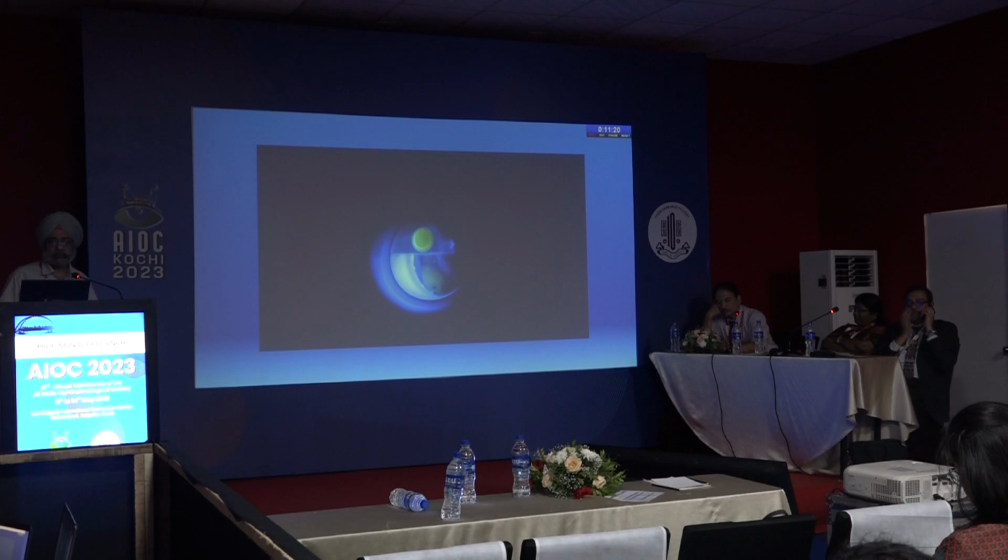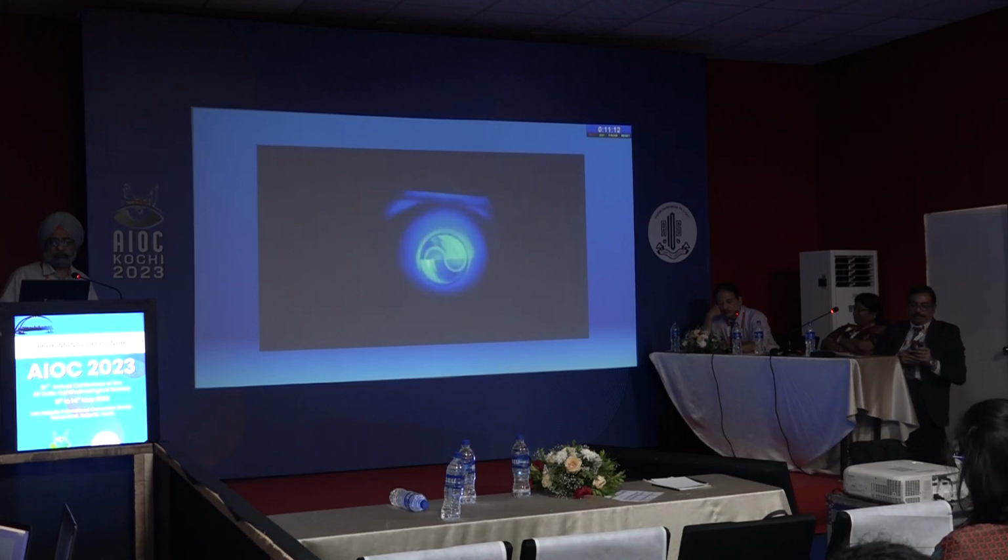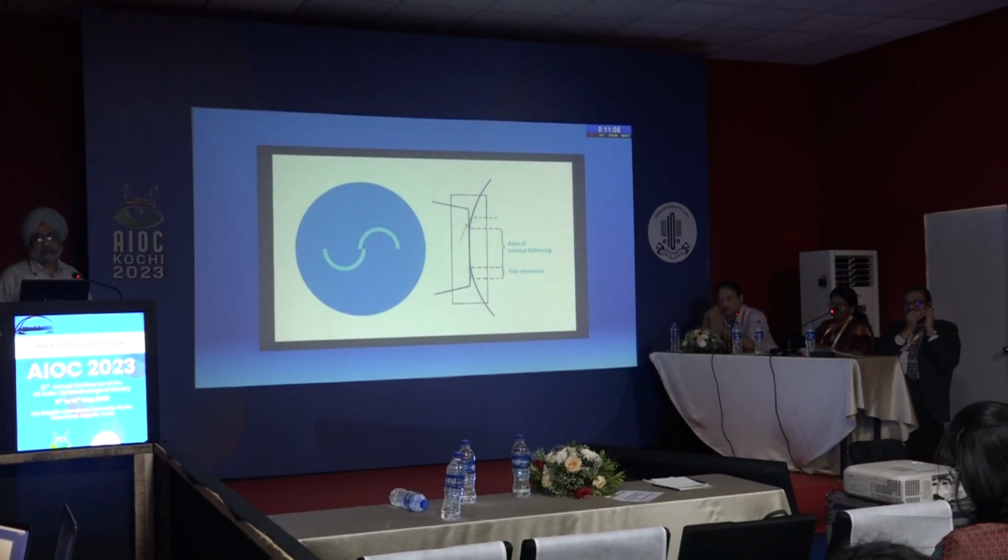On touch, the tear film appears as a bright yellow-green spot which turns into semicircular arcs when the tonometer is moved forwards. When 3.06 mm diameter of cornea is applanated, the semicircles interlock. The thickness of these semicircles represents tear meniscus on the sides of the prism.